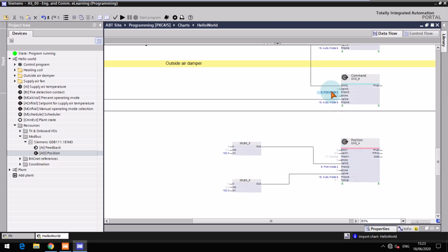Now, I will move the first input source from the binary damper to the first selector block. As it is the global exception from fire detection, it is also the trigger to activate this input source. To copy a connection, use the control key. Hence, in case of fire, the damper will be fully open. The input source for normal operation can also be moved, and it should be always enabled.